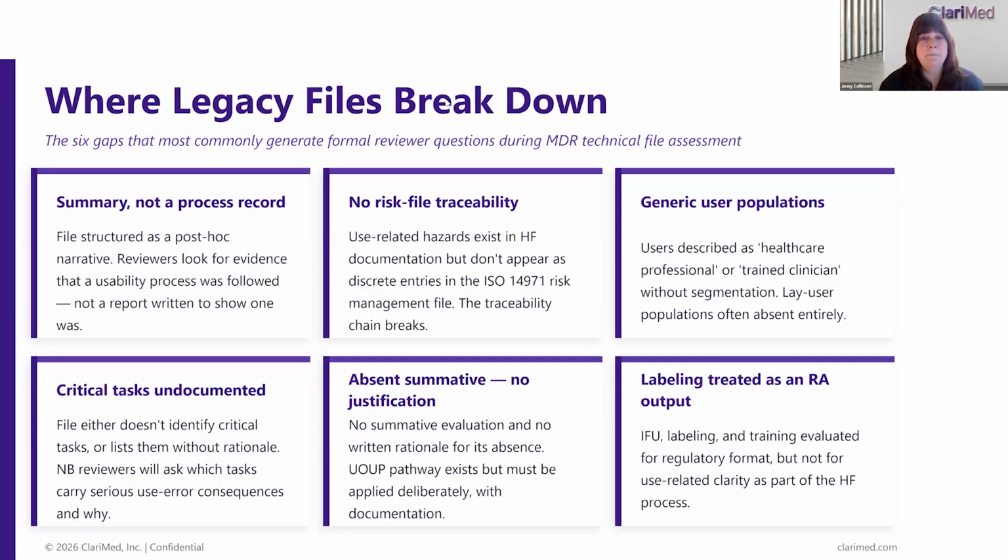And then, as I mentioned previously, labelling needs to be very much part of that human factors process. It needs to be pulled in, assessed, made sure that any labelling IFUs are appropriate for that user group you've identified, and making sure it's part of your usability engineering file. Now, I've mentioned this a number of times, user interface of unknown provenance. So the next slide, we'll just go into that a little bit more, because it's a key step. Louisa, if we can just move on.